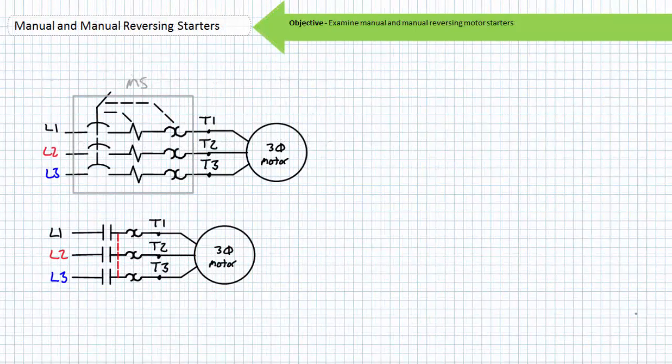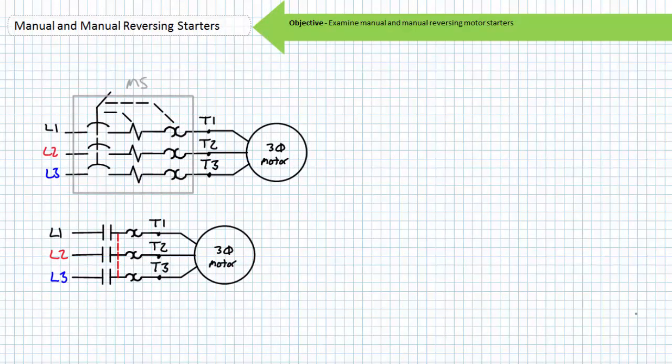Note the schematic symbol for a manual motor starter includes both the symbols for a circuit breaker and an overload. Sometimes you may see additional detection mechanisms internal to the manual motor starter if they include instantaneous overcurrent protection. For example, this manual motor starter includes contacts that are manually, magnetically, and thermally actuated.